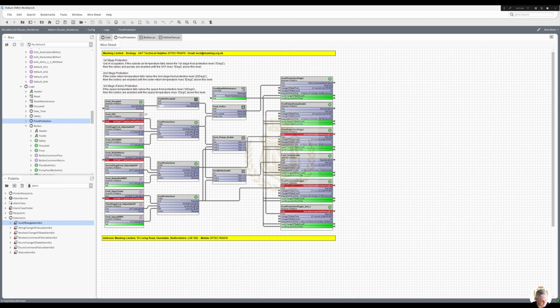So we've got 3 stages of frost protection. Stage 1 is written up here: out of occupation, outside air temperature falls below first stage 1 degree, the valves and pumps are enabled. Second stage and third stage. So third stage is fabric protection, and we'll be looking at the temperature sensor in reception for that.